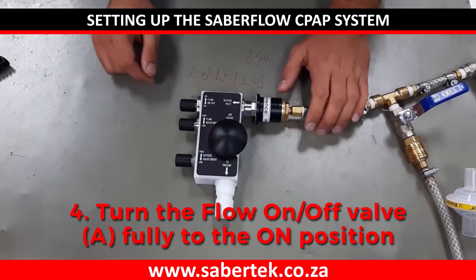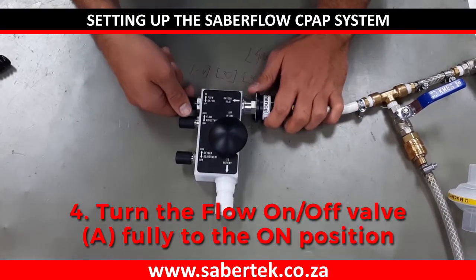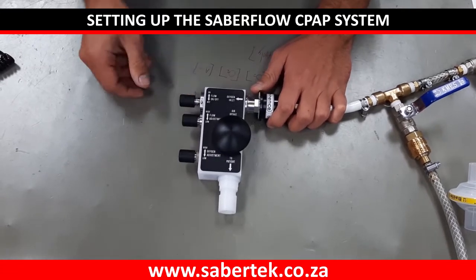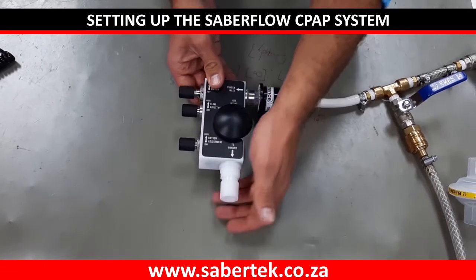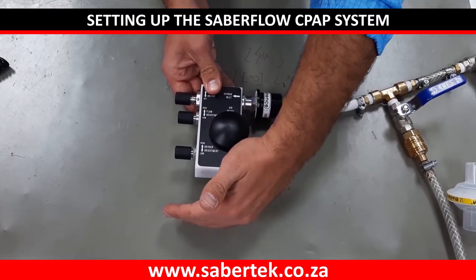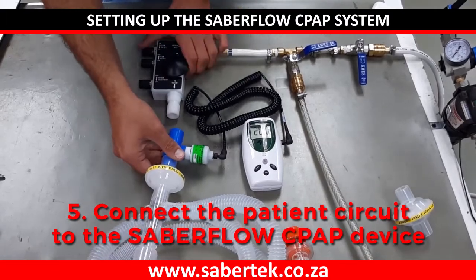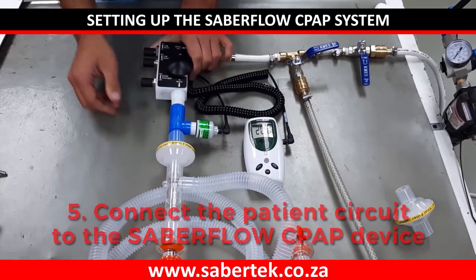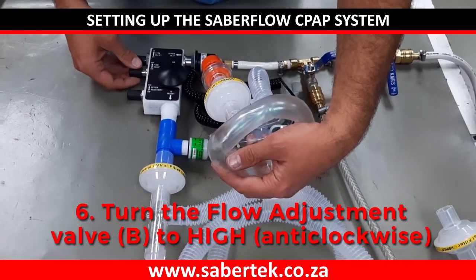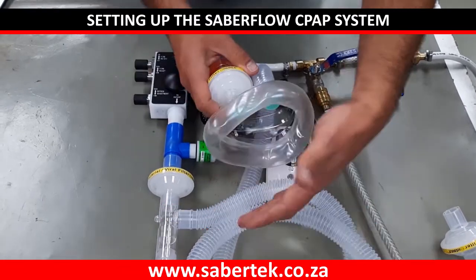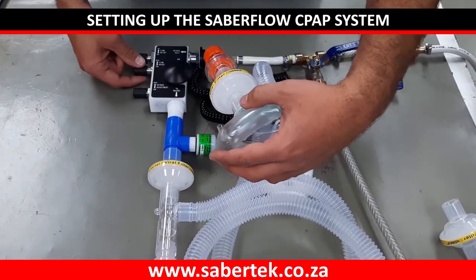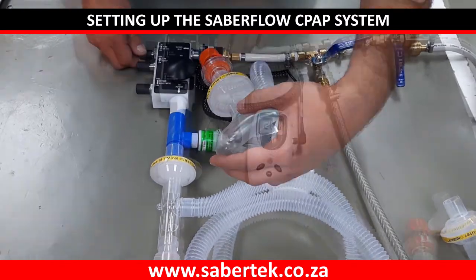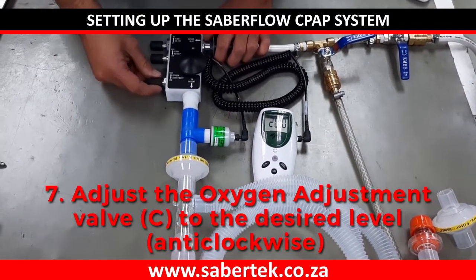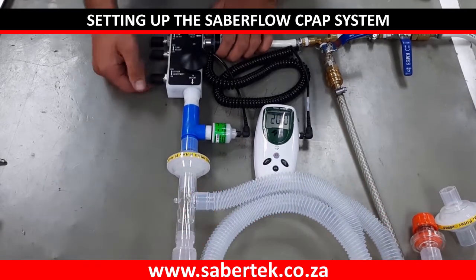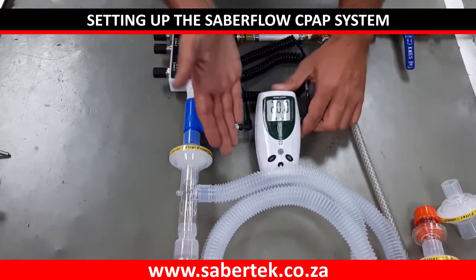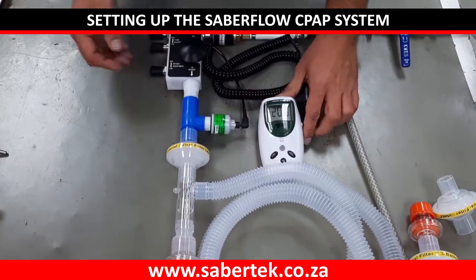4. Turn the flow on-off valve A fully to the on position and ensure that there is no leak or flow from the outlet. This is done by feeling around the SaberFlow's outlet. 5. Connect the patient's circuit to the SaberFlow CPAP device. 6. Turn the flow adjustment valve B to high anti-clockwise and check that the output flow from the patient mask varies accordingly. 7. Adjust the oxygen adjustment valve C to the desired level anti-clockwise as prescribed by the attending clinician and confirmed by the oxygen analyzer.